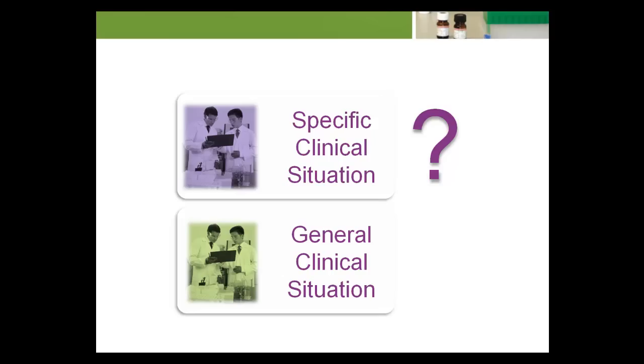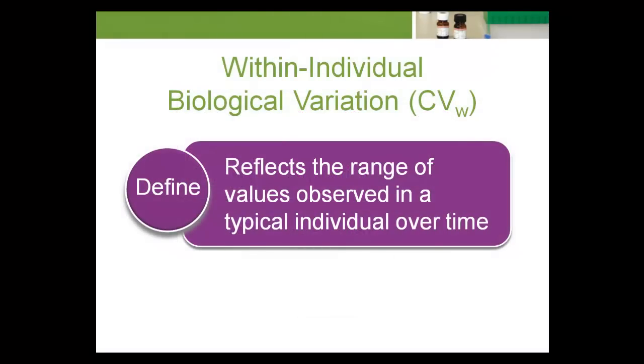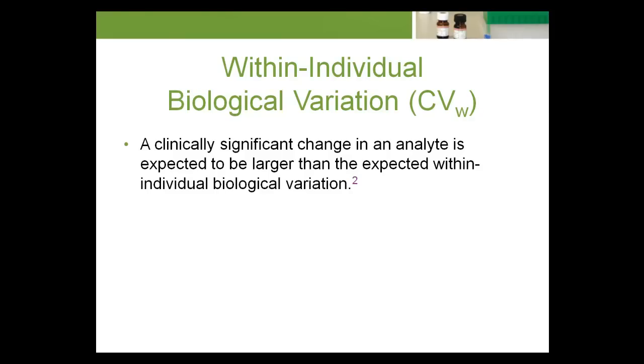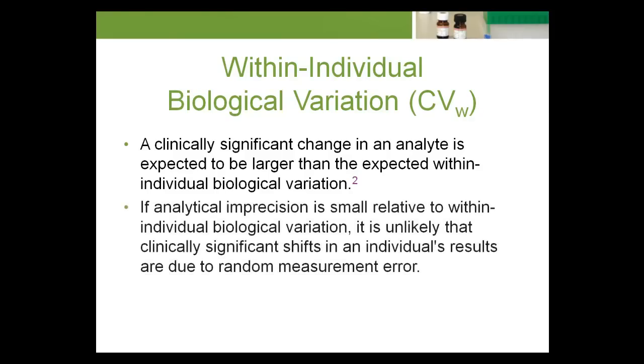One approach is to use knowledge of the within-individual biological variation of the analyte in question to set an upper tolerance limit for allowable analytical imprecision. The within-individual biological variation of an analyte reflects the range of values observed in a typical individual over time. A clinically significant change in an analyte is expected to be larger than the expected within-individual biological variation. If analytical imprecision is small relative to within-individual biological variation, it's unlikely that clinically significant shifts in an individual's results are due to random measurement error.